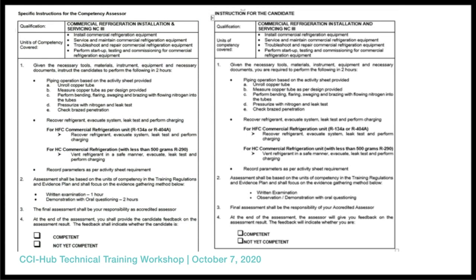This is an example of the activity that a candidate will be performing. This one is an instruction to the assessor, and this one is an instruction for the candidate. So if you will be assessed in commercial refrigeration, you have to perform all of this. You will perform piping, unrolling, cleaning, brazing, and leak testing. You will also perform recovery of refrigerants, leak testing, evacuation, and charging. If you're dealing with HFC, you will perform recovery, leak testing, vacuuming, and charging. But if you will be dealing with hydrocarbon, you will vent refrigerant safely, then evacuate, leak test, and charge. And after that, you will record the parameters.